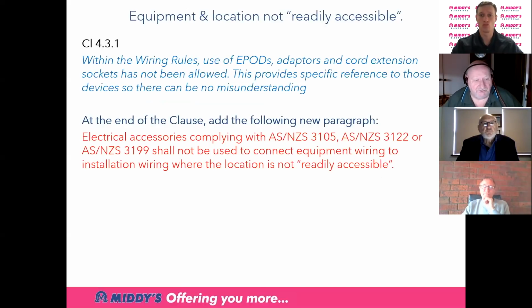Okay, a lot of people, Gary mentioned the 4.13 or the socket outlet in the ceiling. Believe it or not, we had a lot of electricians that thought that was a good way to go: put one in the middle of a ceiling space and then plug in all the EPODs, the electrical portable outlet devices that you buy from your local wholesaler or Woolworths store, and plug as many lights as you like in. We had a big issue with this, so the committee thought about it for a long time, referenced back to the appropriate standards, and realised that they're only permitted to be used where they're readily accessible. So what we've done is include that now as part of the wiring rules. And the bit in red is extremely important: that it shall not be used to connect equipment wiring to installation wiring where the location is not readily accessible. Hidden up on top of the ceiling, in your roof space, is not deemed to be readily accessible, so they are no longer permitted. More work for the electrician. Good job. Okay, can I have the next slide, please?